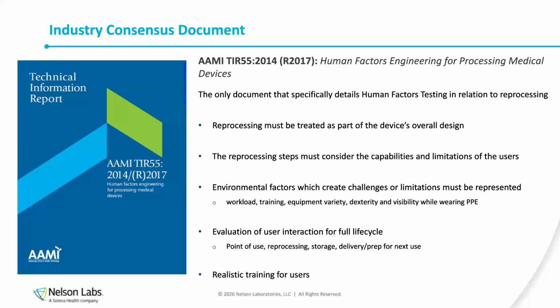You need to consider the capabilities and limitations of the user. Jessica also pointed on this. You know, based on the use of the device and what it's treating, is what you're asking them to do in reprocessing feasible? You do have to consider the environmental factors. Besides just, you know, access to water and where they might be, you have to consider what is the workload of an SPD? Do they have time to really follow these instructions? Equipment variety. If you're calling out something very specific in an IFU for reprocessing, maybe not every hospital or home has that. So definitely be conscious of that.